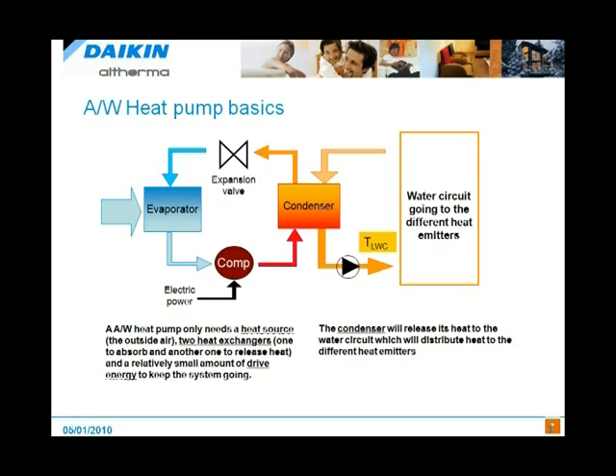So the heat pump basics: what a heat pump does is, using in our case air, extract energy, employed within a refrigeration process where the power into the unit is into the compressor, and this change of state that occurs in the evaporative and condensing process is where there's a great energy boost that is much, 300% greater than if you just burn natural gas or fuel oil directly.